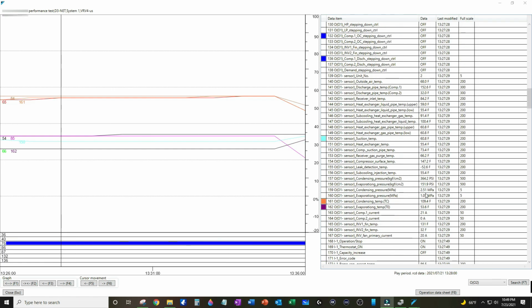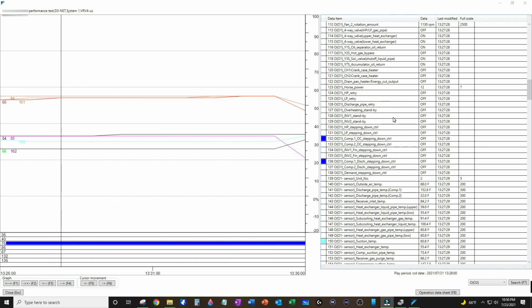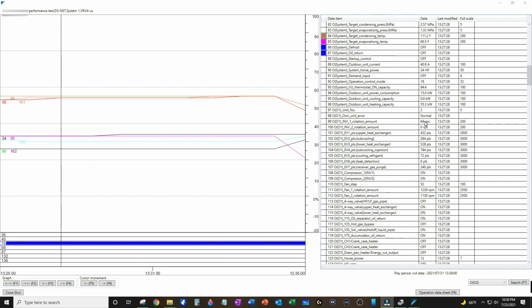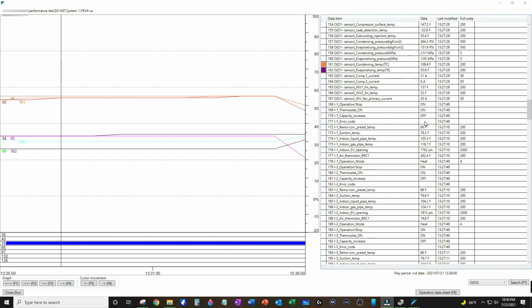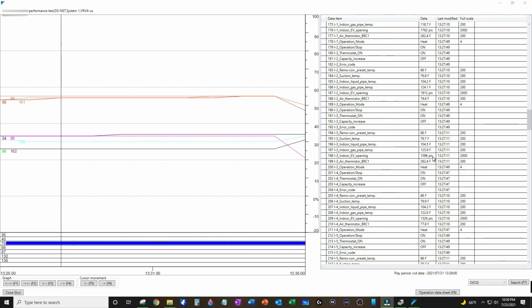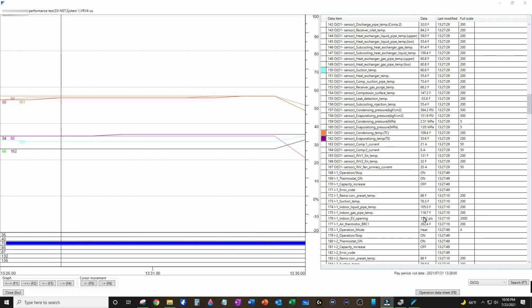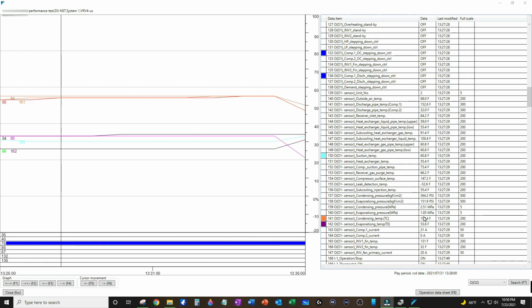I'll typically make this loop several times during the course of an hour or more, depending on how good the data looks. It's also important to note that I'm looking at way more stuff than what we just breezed through. There's compressor RPS, indoor EEV positions, subcooling heat exchanger data points at the outdoor unit, suction temperature at the outdoor unit as well, amp draw, fan speed, safeties. Like I said before, about 2 days worth of training to get through all of these points. But at the end of the day, things are looking okay.